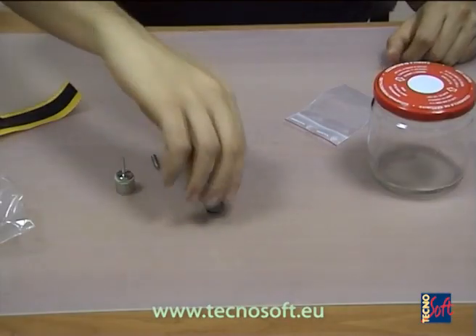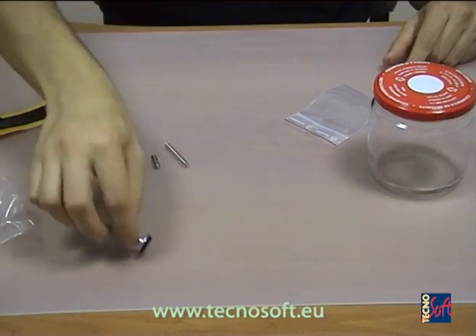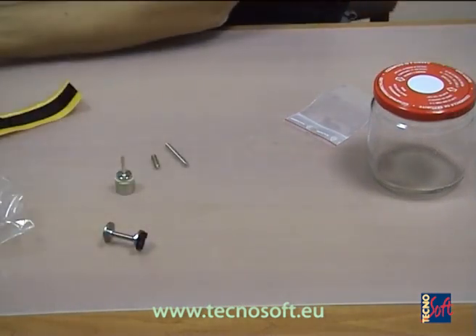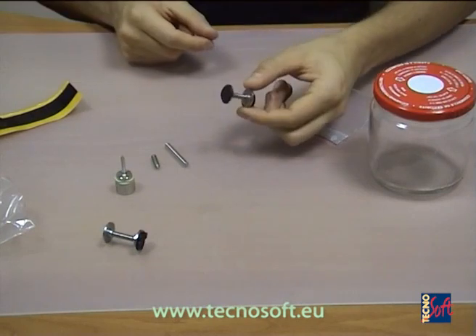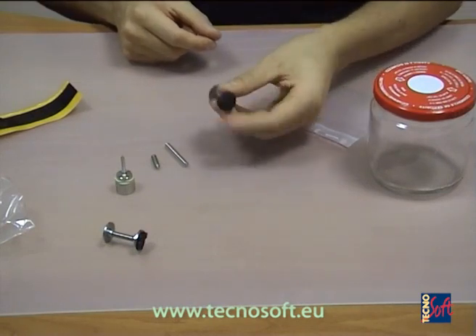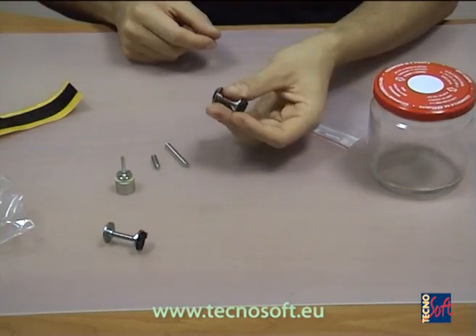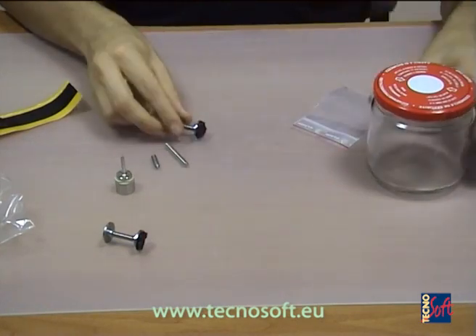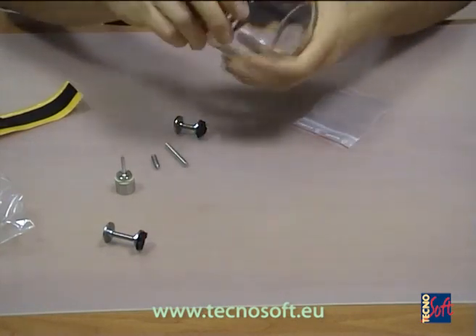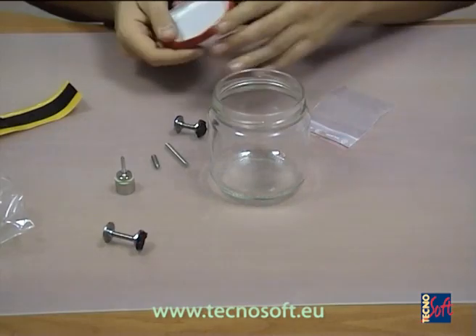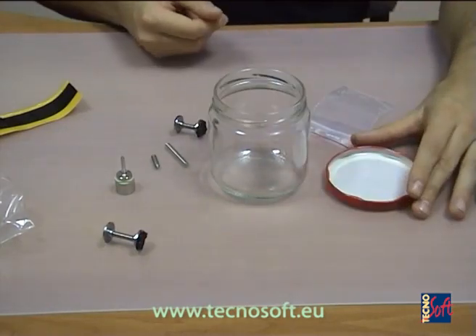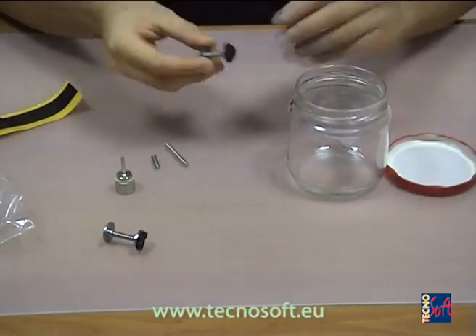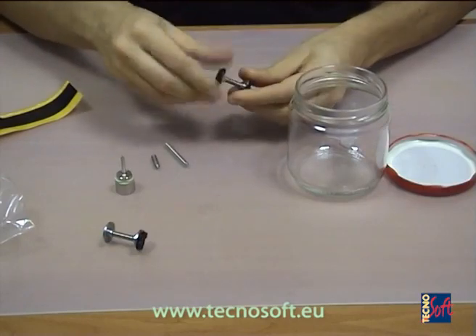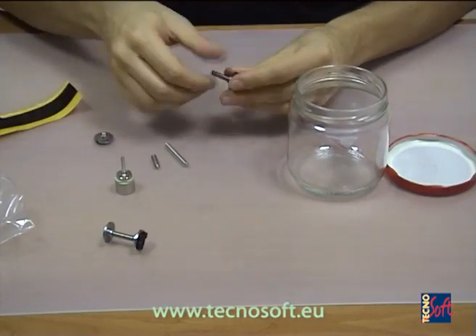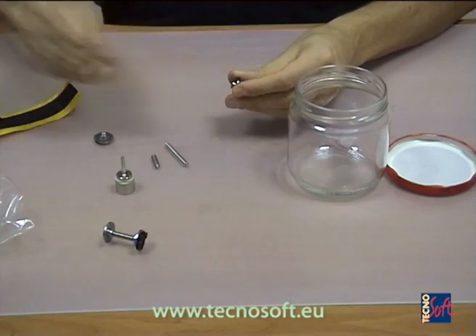Now we are going to place an S-micro logger inside a jar. In this example, a jar filled with a solid or semi-solid product, so the tip of the probe, which has the sensing point, must stay at the center of the jar. We must use the proper pivot, in this case the 1 centimeter pivot.